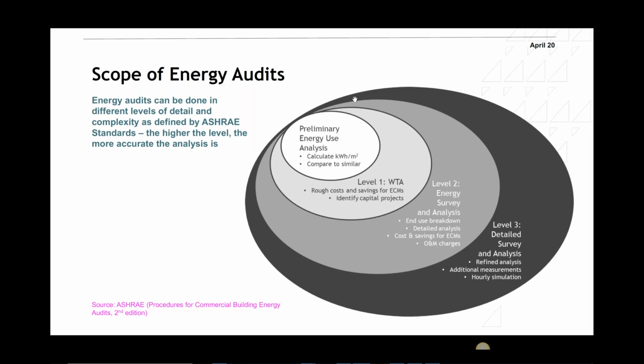So there's the preliminary energy use analysis. That's mainly to calculate your EUI, or the energy use intensity, or Energy Utilization Index - we call it EUI. That's basically looking at the whole energy consumption for a year, let's say, dividing that by the square meter, normally the air-conditioned area or the GFA, and that would be the EUI.